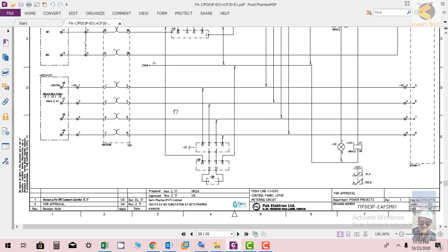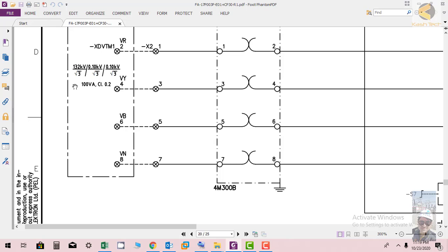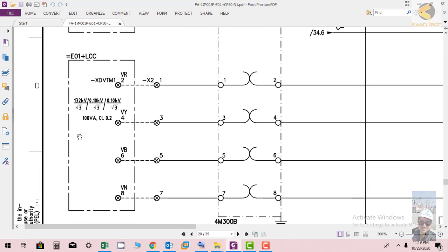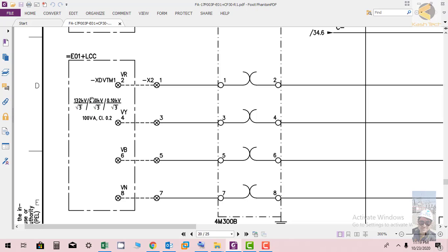Now we'll check the VT circuit. VT is also coming from LCC E01 plus LCC. It is coming from XDVTM1 with three phases red, yellow, blue and neutral. The VT has primary side 132 KV, secondary side has two cores, 0.1 KV by 0.1 KV means 100 volt by square root of 3. Rating is 100 VA and class is 0.2.